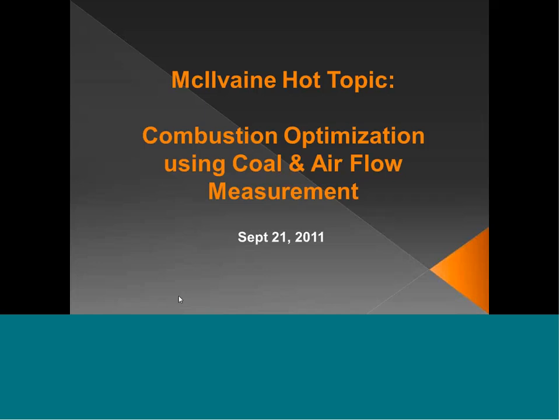Okay. And again, why are people doing this? What we want to be able to do, and we can do now, if somebody has our coal flow system, they can look at the average velocities on each mill and pretty much infer, if one mill has very low velocities for the same mass flow, odds are its fineness is bad, and that's probably the next mill I'm going to want to service. Yeah, absolutely. You could start doing better predictive maintenance on your overhaul cycles because the fineness level's dropping. Right. Okay. Thank you.